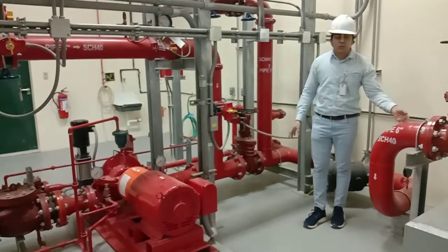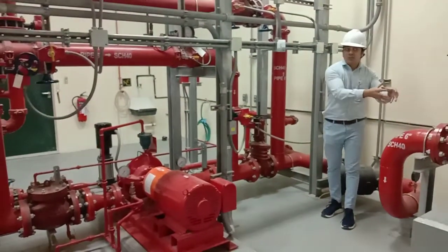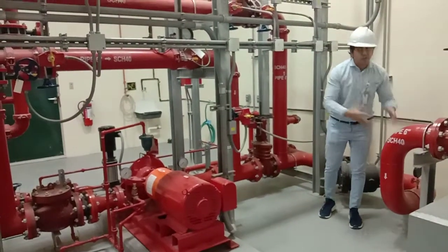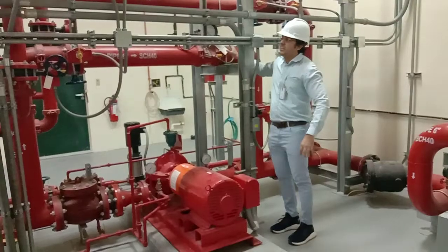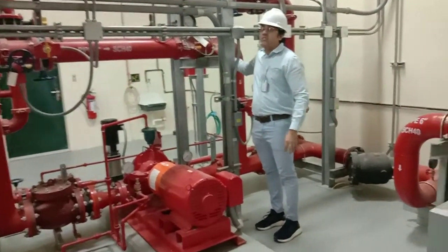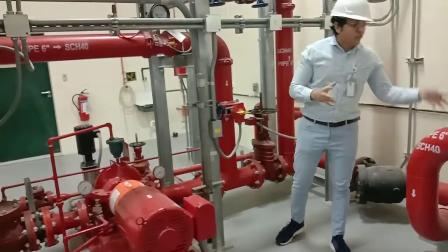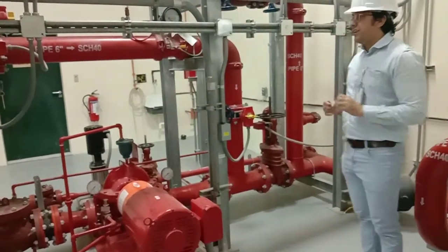Maybe there is some scale build up inside the piping, and there might be some foreign material that will obstruct the supply, right? Or maybe some kind of blockage inside the pipe. We don't know that. For that reason, this is not acceptable for the acceptance test of the pump; every 10 years, we need to make sure regarding the suction supply. So this is all about the closed loop metering device.